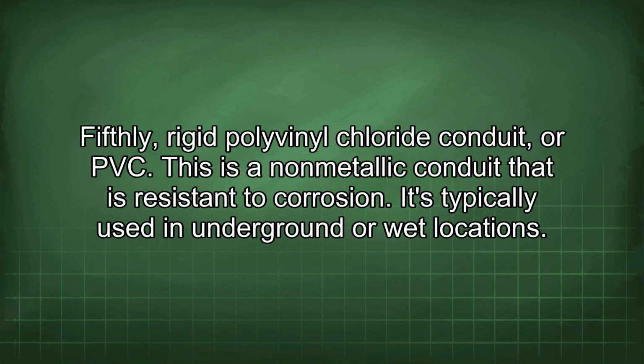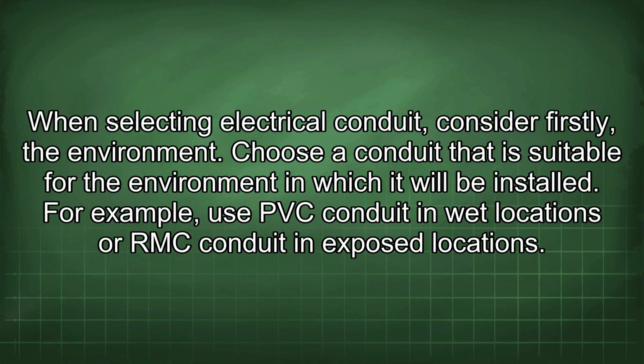Fifthly, rigid polyvinyl chloride conduit or PVC. This is a non-metallic conduit that is resistant to corrosion. It's typically used in underground or wet locations. When selecting electrical conduit, consider firstly the environment. Choose a conduit that is suitable for the environment in which it will be installed. For example, use PVC conduit in wet locations or RMC conduit in exposed locations.